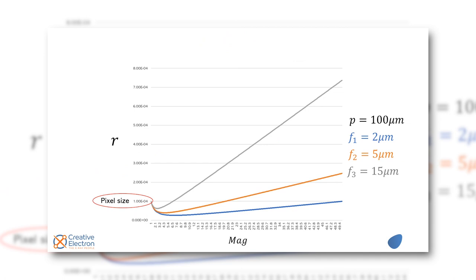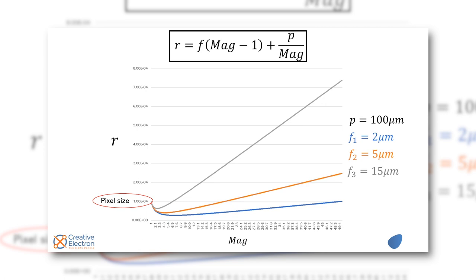Let's play a little bit more with the numbers so you can see different equations and different impacts. This is a situation where we have a detector with 100 micron pixels and three different sources: two micron spot size, five micron spot size, and 15 micron spot size. And you can see the drastic difference, so this is 15, this is five, and this is two microns.